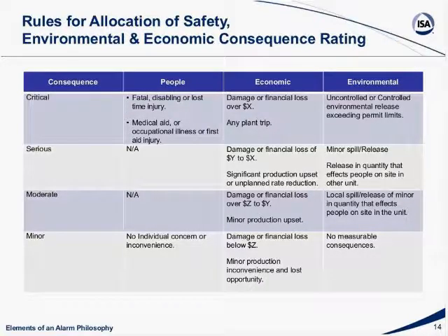Because typically these would fall into this situation. For example, you get an alarm, a safety shower activation out in the field. If somebody's using a safety shower, you need to get help to that person out there immediately. So that immediately becomes the highest priority. And with regards to people, those are the only alarms. They're the critical alarms because somebody is in harm's way.